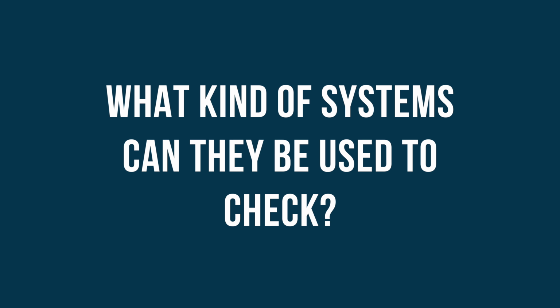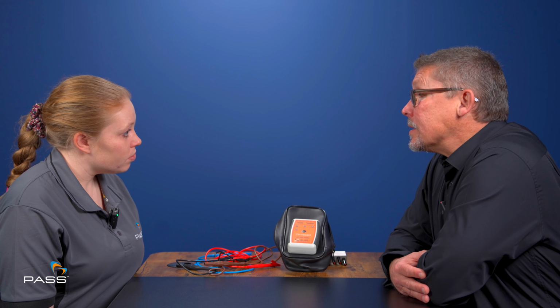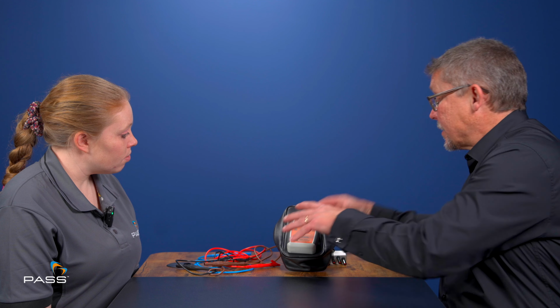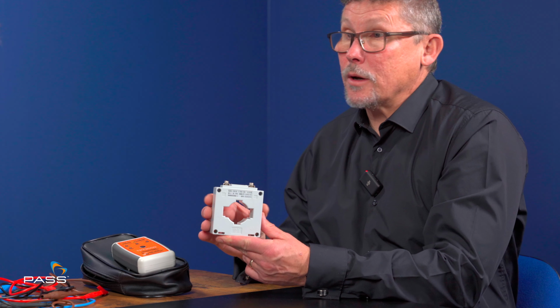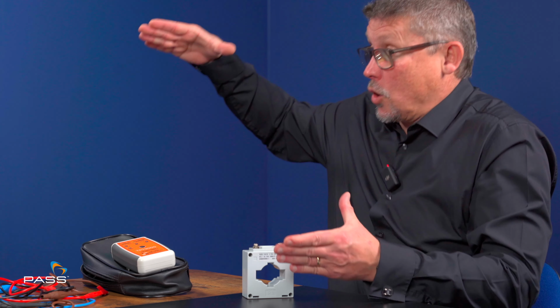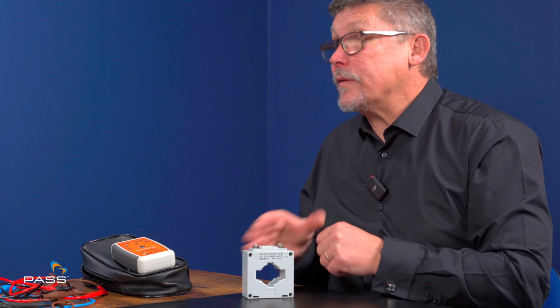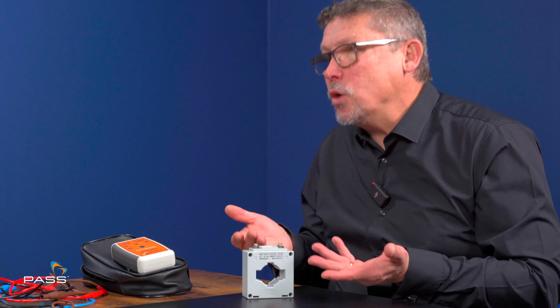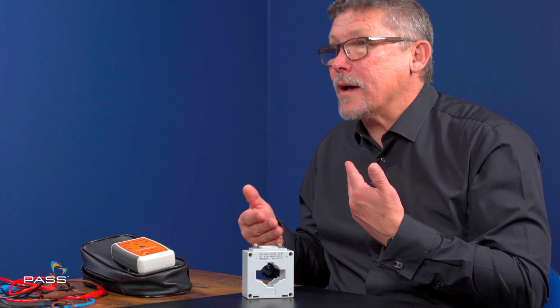So what kind of systems can they be used to check? Is it high voltage, low voltage, medium voltage? It's any of the systems that would utilise a CT. A CT could be this small or that large. Alternatively, it could be a voltage transformer. They look a little bit different, but they still have a direction.